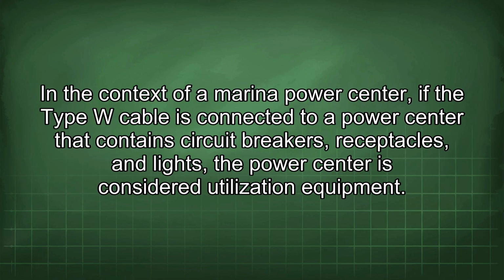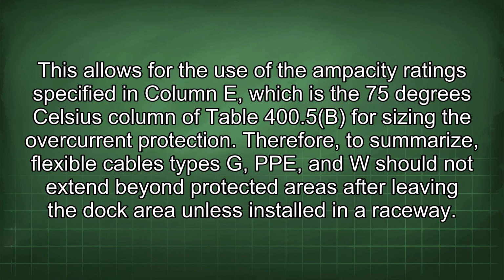In the context of a marina power center, if the Type W cable is connected to a power center that contains circuit breakers, receptacles, and lights, the power center is considered utilization equipment. This allows for the use of the ampacity ratings specified in column E, which is the 75 degrees Celsius column of Table 400.5b for sizing the overcurrent protection. Therefore, to summarize, flexible cables types G, PPE, and W should not extend beyond protected areas after leaving the dock area unless installed in a raceway.